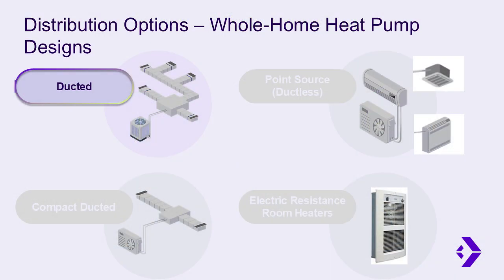Unlike traditional fossil fuel systems, heat pumps offer greater flexibility in distribution options. This makes it easier to create innovative solutions tailored to a home's layout. But remember, great design isn't a substitution for right sizing. Right sizing the system is critical to ensure the capacity at design conditions matches the calculated design load, delivering optimal performance. We'll talk more about this later on, but system pairing is a key driver of heat pump design. Pairing indoor units with spaces that share similar heating needs boosts both efficiency and comfort, while strategic outdoor unit placement ensures proper airflow year-round, enhancing reliability and extending the system's lifespan.